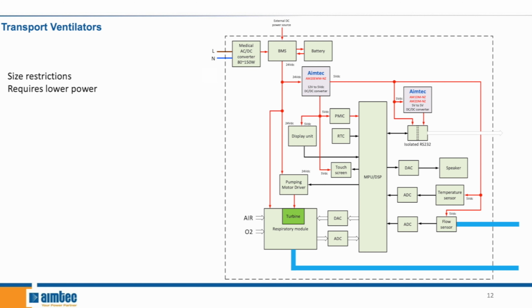Next, we have the transport ventilator. Since it's meant to be transported, this is much smaller than the previous ventilator. Since it's smaller, it only requires about 80 to 150 watts of power. In the block diagram, we see that the device is powered by an onboard medical-grade AC-DC converter or an external 24-volt medical-grade adapter. The 24 volts from the onboard AC-DC or external adapter powers the motor and the valve directly.